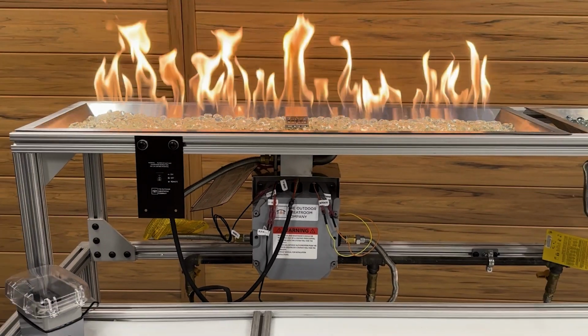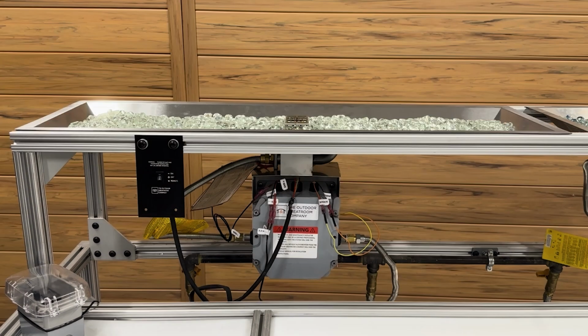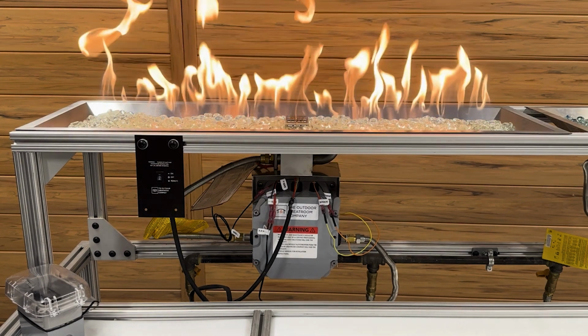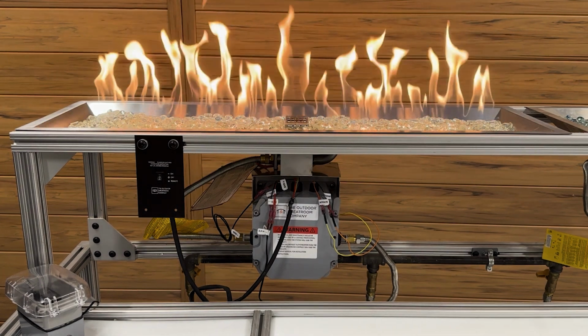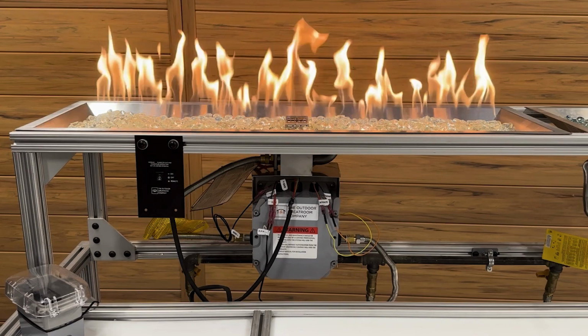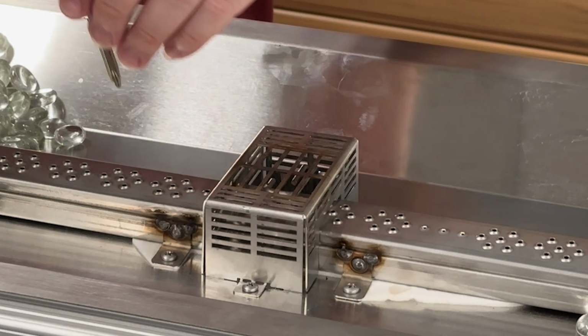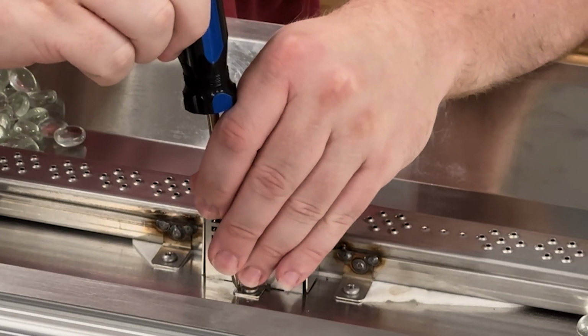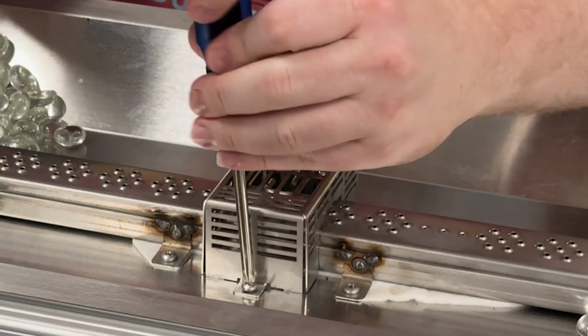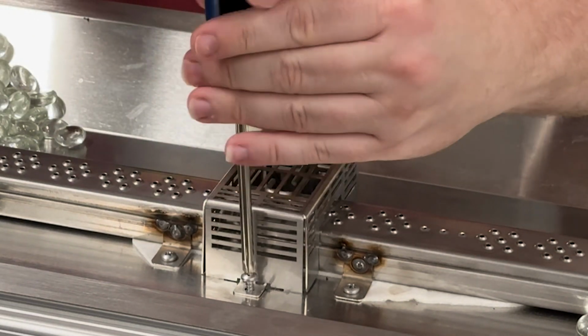While in operation, the module is constantly receiving a signal to determine if a flame is present. If a flame is present, the system will simply stay on. If the flame signal is ever interrupted, the module will begin to spark again to reignite. When the system regains the flame signal, the sparking will stop. The system will shut down if a reignition attempt goes longer than 12 seconds. It is also possible for a film to build up on the flame sensor and ground rods that can cause this signal to fail and not properly sense the flame.